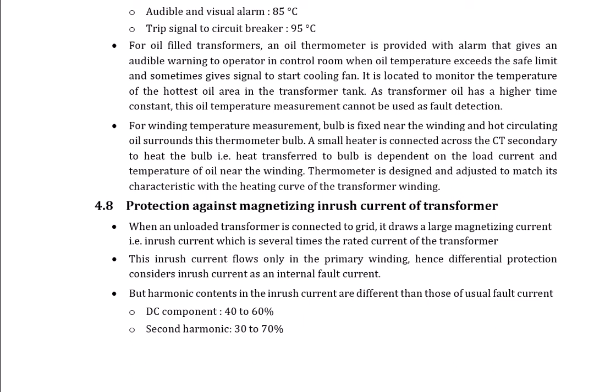So if we use the differential protection, it would operate, but the inrush current is normal when the unloaded transformer is connected to the grid, so we do not treat it like a fault.